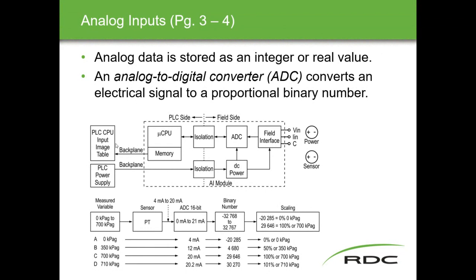Starting with analog inputs — analog data is stored as an integer or a real value, either a whole number or a number with a decimal place. An analog-to-digital converter is the component inside the AI module that converts the electrical signal from a field device, like a transmitter, into a proportional binary number. This is all within the AI module in the rack — your Allen Bradley, Honeywell, Delta V, or whatever it happens to be. The AI module connects to the processor of the PLC and shares data back and forth.